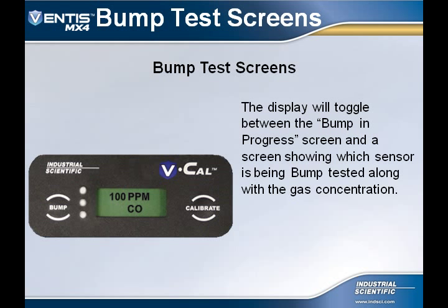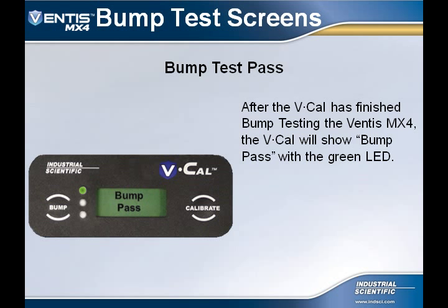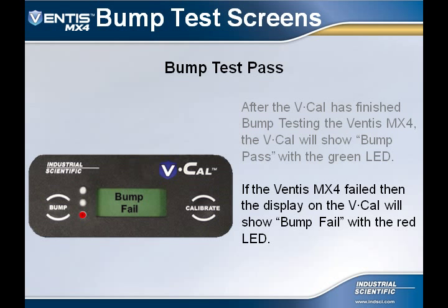The display will then toggle between bump in progress and the sensor being tested next, as well as its bump gas concentration. And finally, the display will toggle between bump in progress and the last sensor type being bump tested, as well as its bump gas concentration. After the bump test is finished, the VCal will show bump pass on the display with a green LED. If the bump test failed, the VCal will show bump fail on the display with a red LED.